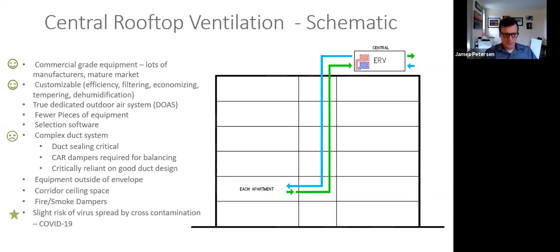But the important thing to point out is that these are 100% outside air units, as opposed to recirculating equipment, which is the most common type of air system in buildings, all types of commercial buildings specifically. So these are all three 100% outside air approaches to ventilation. So I've gone over a little bit on my 10 minutes. It's time for me to hand it over to Tom. And this is just a summary of the things we just talked about.